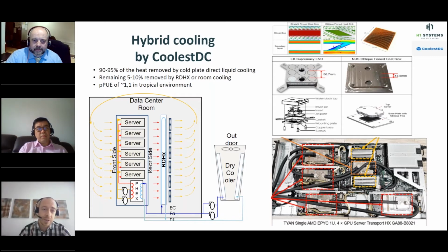And the PUE you can reach with this, just focusing on cooling, is also significantly less - that's quite obvious. But going back to my previous answer, you can actually control the processor junction temperature more precisely with this cooling, which enables you to do more computing from the same hardware, or reduce your hardware's processor energy consumption by maintaining lower temperatures at the junction. You cannot do that with traditional cooling, so you're forced to rely on data only.